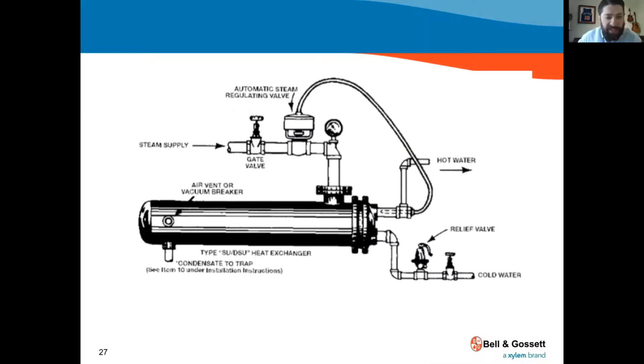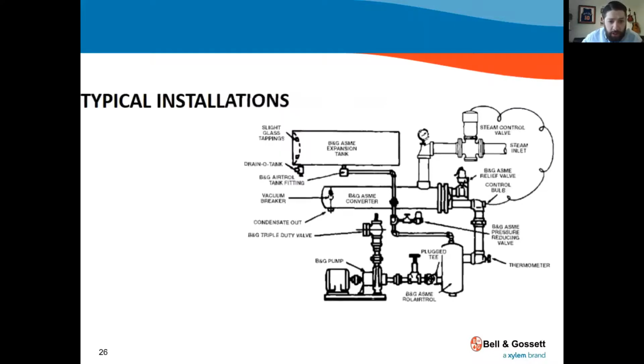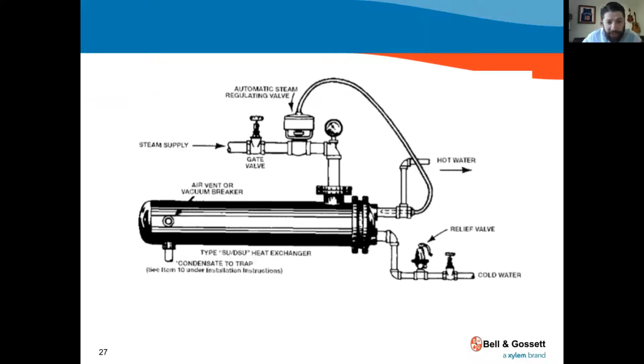So here's the automatic steam regulating valve, and that's showing you that it's got a connection to the hot water out. So this one's controlling by the temperature there. It's tracking the temperature on the way out and making sure you've got the right temperature needed. As you see on the far left, air vent or vacuum breaker. That is where you must have a vacuum breaker installed.